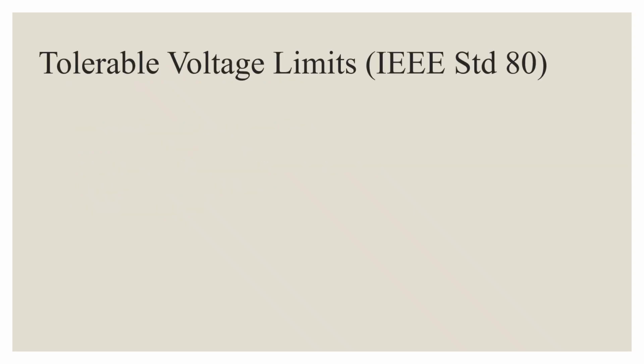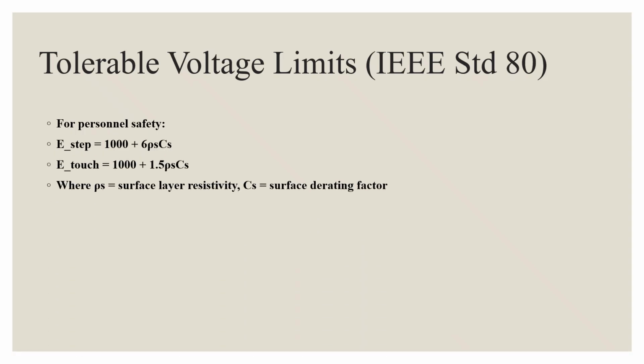So to maintain safety, we compare calculated voltages with tolerable limits as per IEEE standards. These are the formulas, where ρS is the surface resistivity and Cs is the derating factor for surface material like gravel. If the actual voltages are below these limits, the system is safe for human contact.